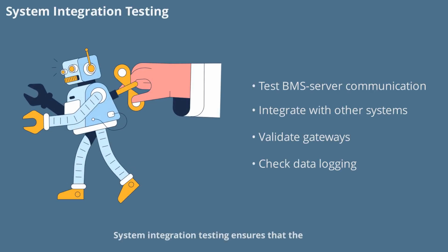System integration testing ensures that the BMS communicates seamlessly with other building systems. We test connections between BMS controllers and servers, as well as integration with fire alarms, HVAC, lighting, and meters. Gateway configurations are validated, and we confirm that data logging and trending are working correctly. This step is crucial for a unified building management experience.